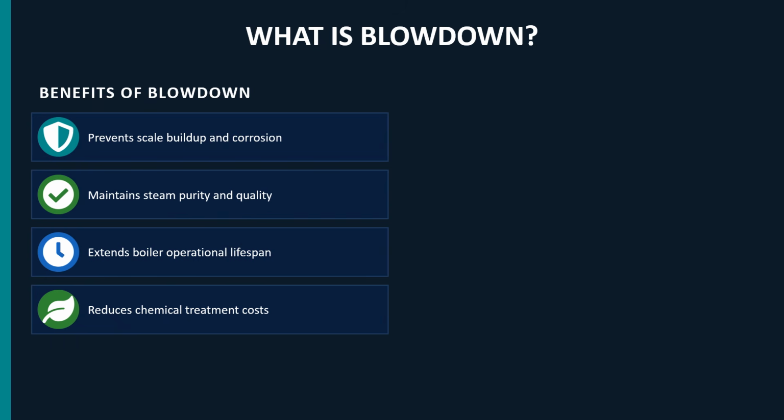Benefits of blowdown. Proper blowdown offers several important benefits. It prevents scale buildup and corrosion. It improves steam purity and quality. It extends equipment life by reducing overheating and damage, and it lowers chemical treatment requirements. Simply put, effective blowdown improves both boiler performance and reliability.